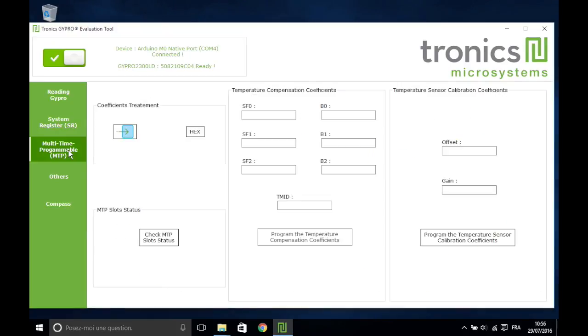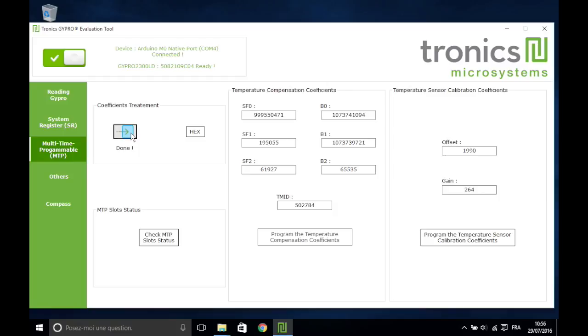The MTP tab is useful for permanent programming of new temperature coefficients into the sensor. First, you need to transfer the coefficients from the System Register tab by clicking on the blue button.